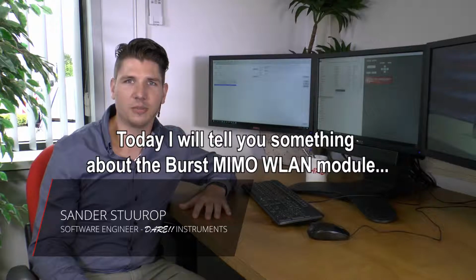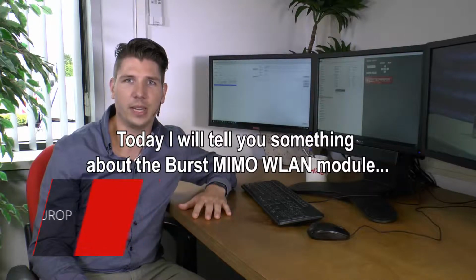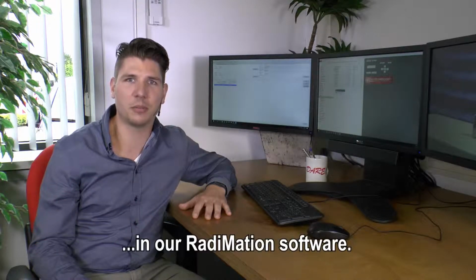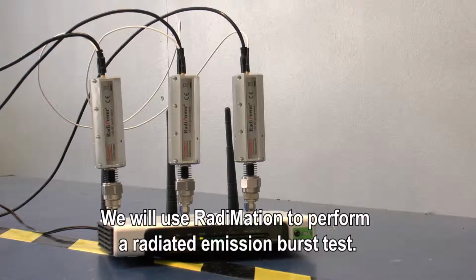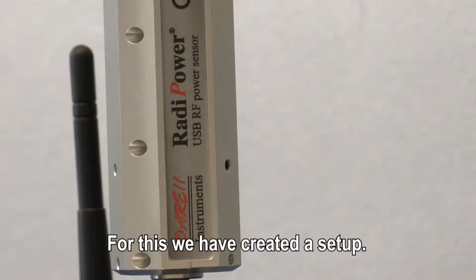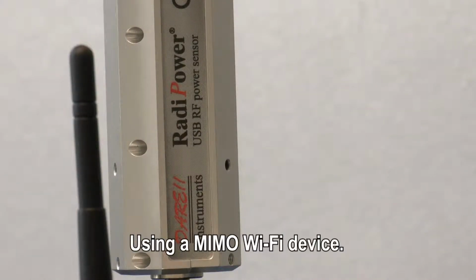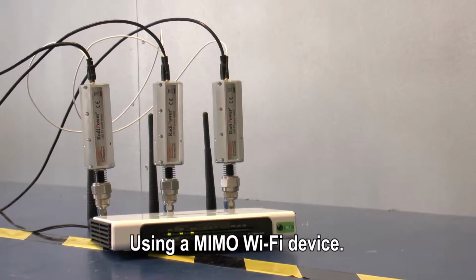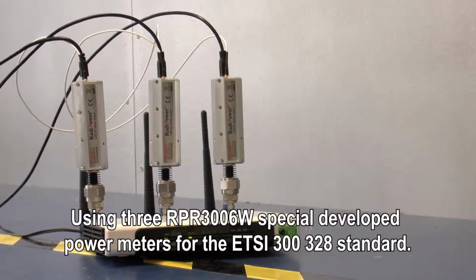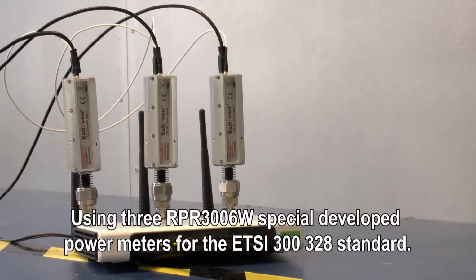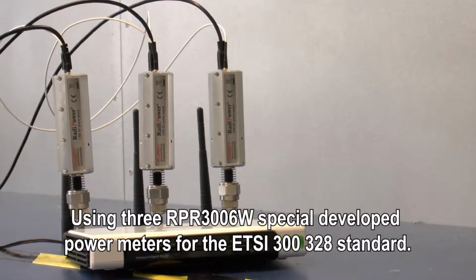Today I will tell you something about the Burst MIMO WLAN module in our RadiMation software. We will use RadiMation to perform a radiated emission burst test.